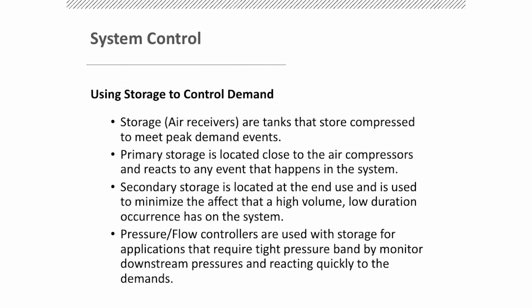But the point is, that's when you're going to spend most of your time. And what do we usually do when we size equipment? Well, we have to make sure we serve that demand, so it's got to be sized for that. And typically, it's just like any other system you see out there, whether it's pumps, boilers, chillers, HVAC, it doesn't matter. It seems like whatever engineer is going in makes sure that there's a safety factor on it. And depending on how many times it gets reviewed, that's how big it gets. And you have to be concerned with that. So again, understanding what the actual needs are and what the intent is. So again, the controls are important.